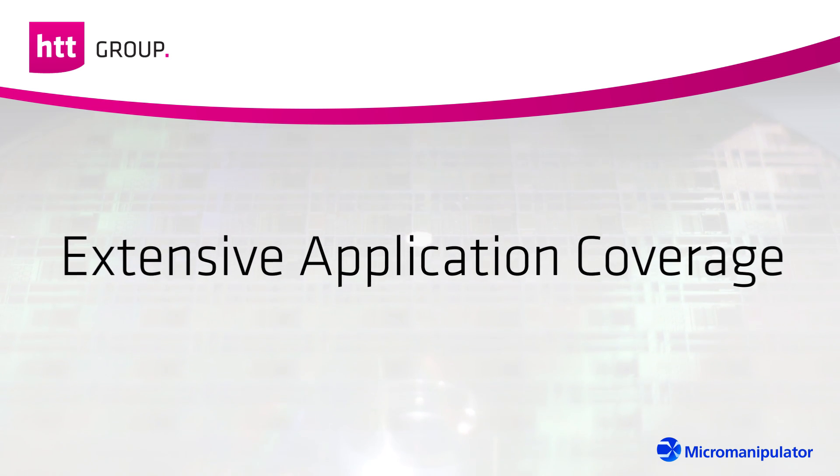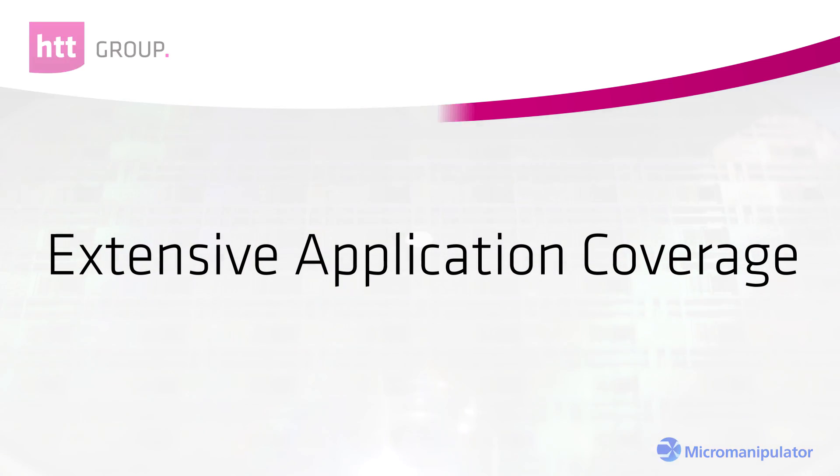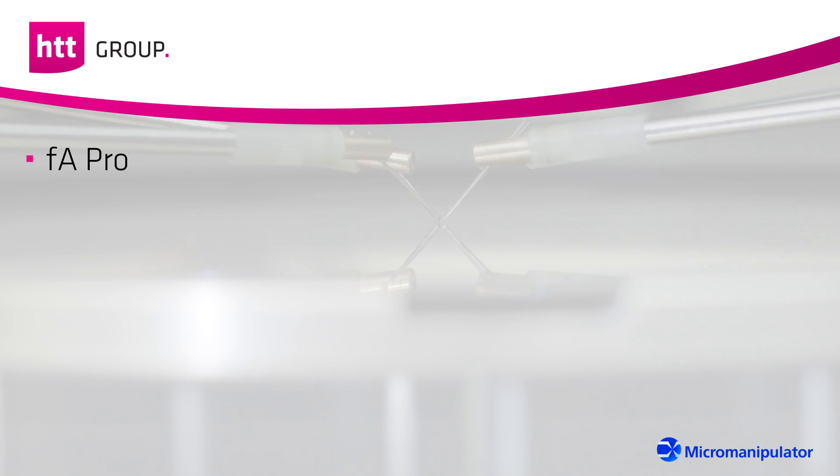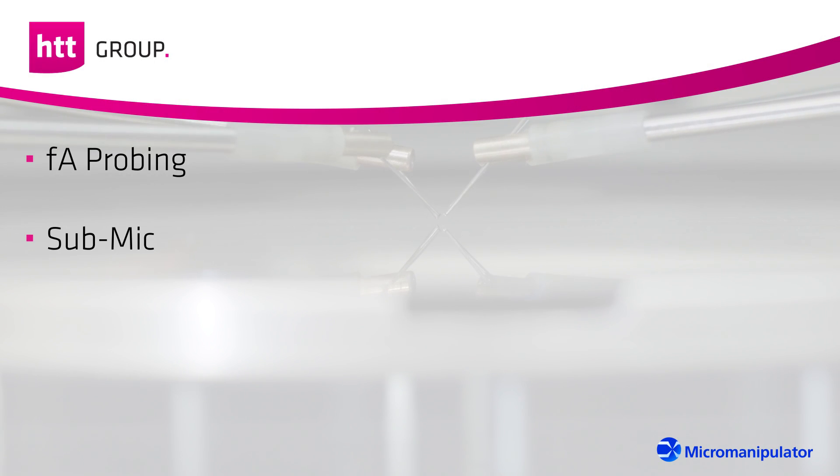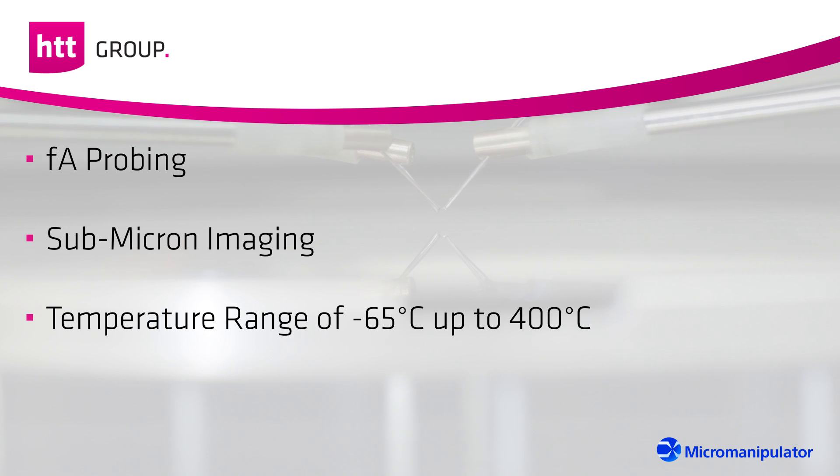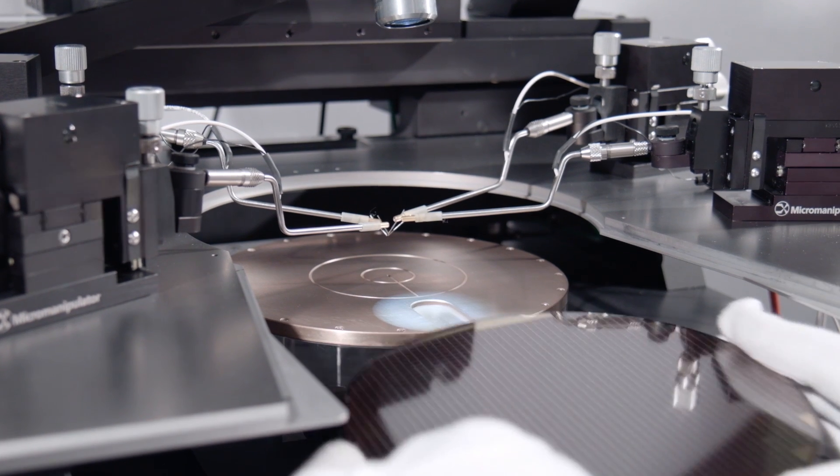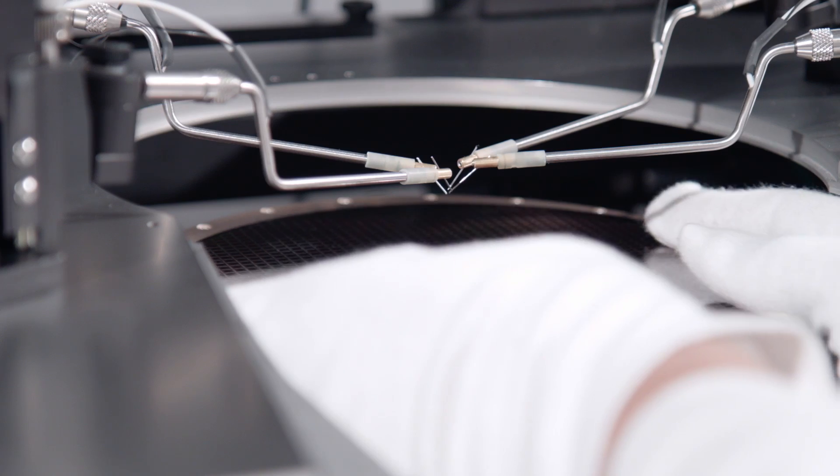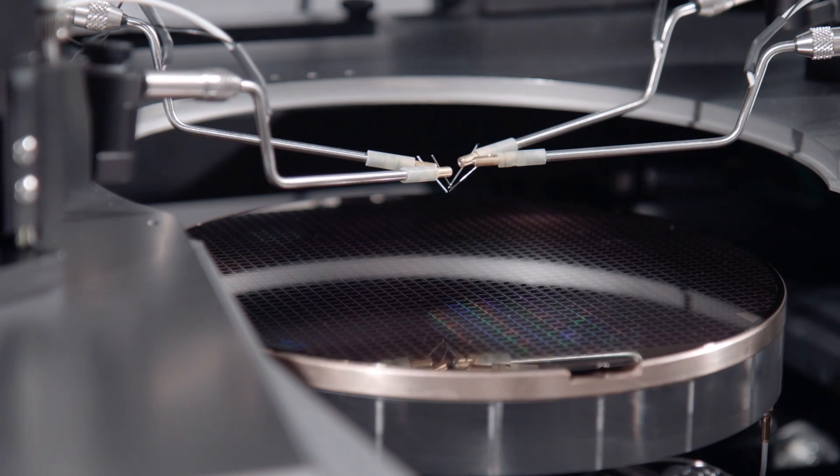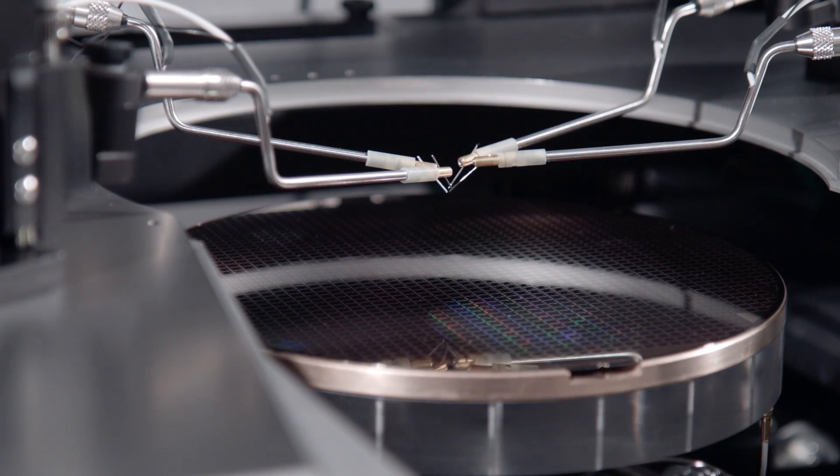Manual probe stations allow the user to perform femto ampere range probing and sub-micron imaging in high and low temperatures. High precision semi-automatic probe stations feature a comprehensive software suite, touchscreen panels, and user script compatibility.